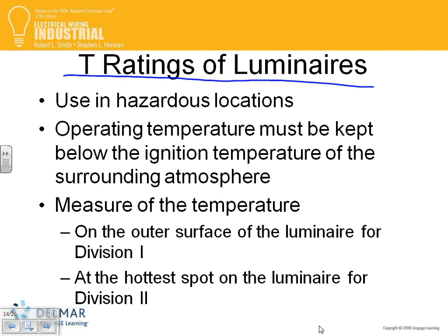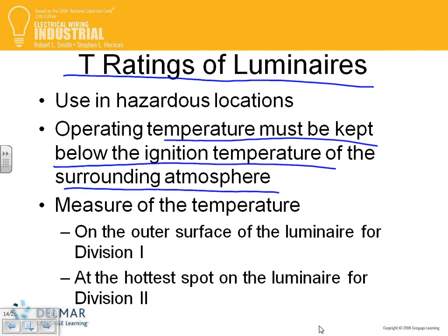FYI, so that's basically operating temperature kept below the ignition. This is a key point. Operating temperature must be at all times kept below the ignition temperature of the gas or the dust.